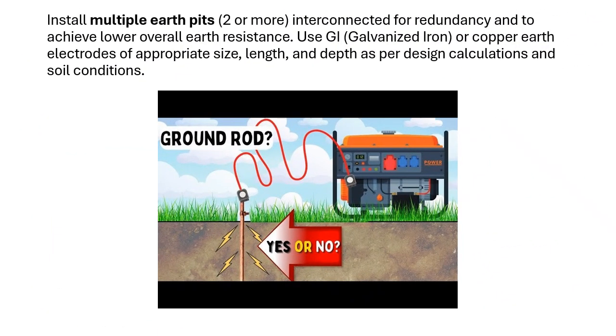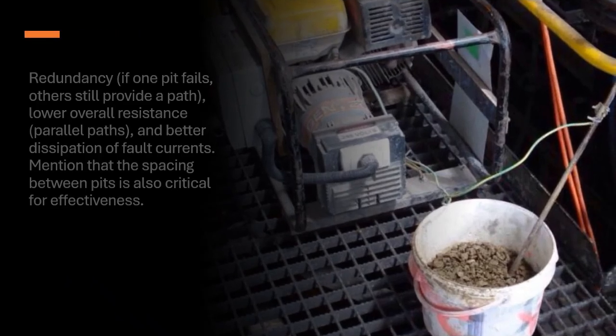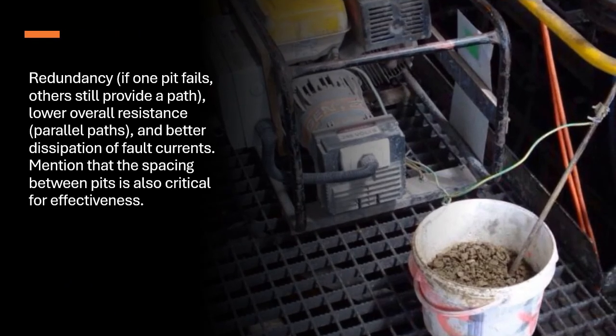Multiple earth pits and electrodes. Install multiple earth pits, 2 or more, interconnected for redundancy and to achieve lower overall earth resistance. Use GI, galvanized iron, or copper earth electrodes of appropriate size, length, and depth as per design calculations and soil conditions. Redundancy: if one pit fails, others still provide a path, lower overall resistance, parallel paths, and better dissipation of fault currents. Mention that the spacing between pits is also critical for effectiveness.